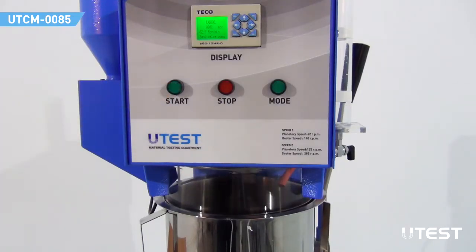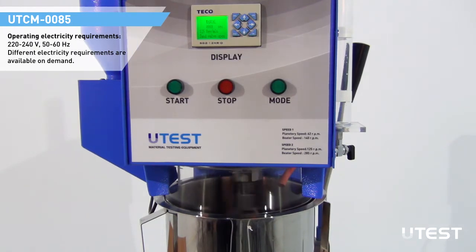The device has two controlled speeds. In low speed, the mixing paddle revolves at a rate of 140 RPM with a planetary motion of 62 RPM. In high speed, the paddle revolves at a rate of 285 RPM with a planetary motion of 125 RPM.